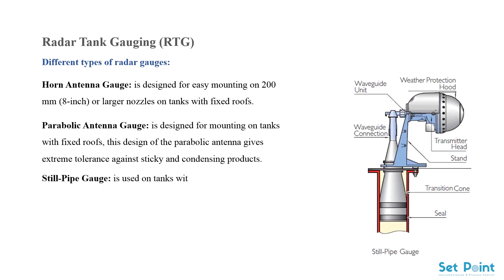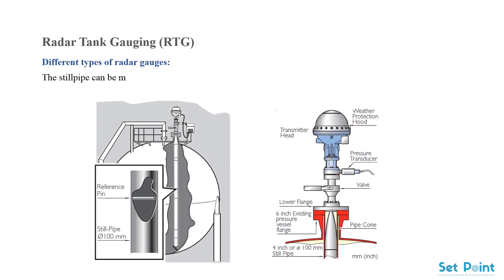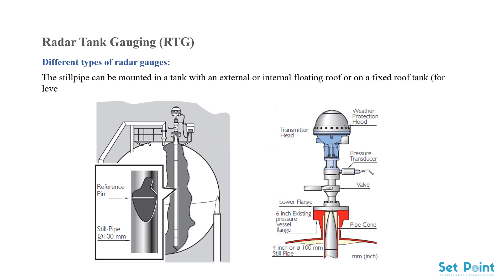The still pipe gauge is used on tanks with still pipes and with all compatible products such as crude oil and gasoline. It transmits radar waves from a cone-shaped antenna towards the liquid surface inside the pipe. The still pipe can be mounted in a tank with an external or internal floating roof, or on a fixed roof tank for level measurement of liquefied gas in LPG or LNG tanks.